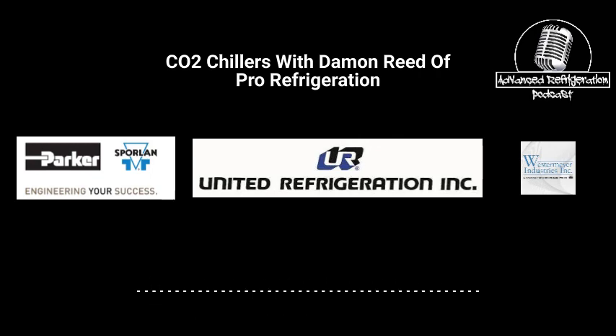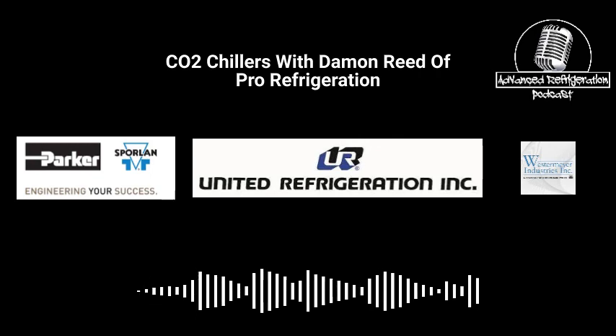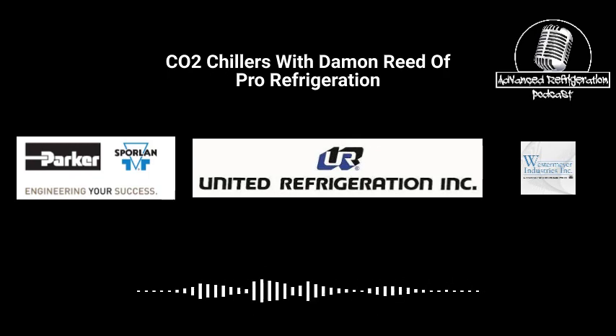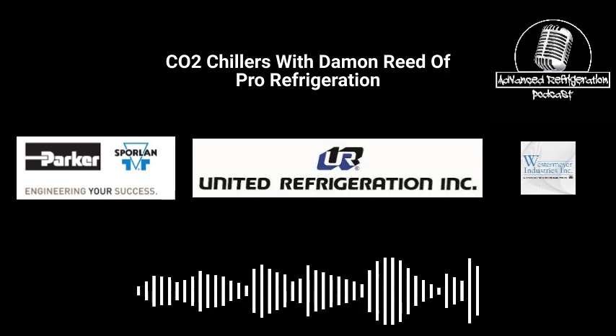Wow. So how much energy savings? Because I'm thinking that with all the energy that you're saving, one chiller is basically a zero net sum game, right? Because you're cooling for free. You're using that total heat rejection. You're killing the amount of energy that you're using on your gas cooler because you're not using it most of the time. And then the amount of propane that they're not burning because of that, plus that savings, and then the energy that they're going to save because of, like you said, the emissions. You probably get green credits for that as well, right? Yeah, those things are all being.